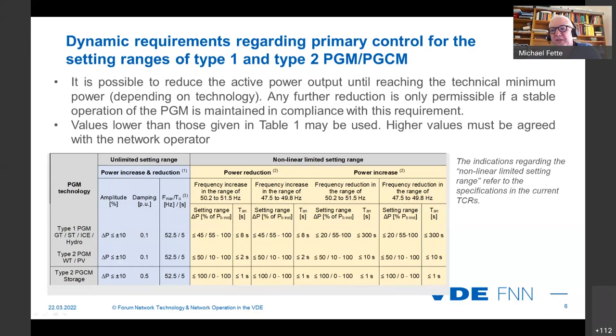We are looking exactly for the damping characteristics which each controlled unit could contribute to the grid. Therefore we asked the manufacturers, how good and how able are your plants, your PGMs, and how could they support the grid? In which case should they do that? And which portion of damping can they add to the grid behavior? These are questions which are very difficult to answer. We know from the manufacturers that some have no idea how to answer these kinds of questions, especially the smaller manufacturers or those of smaller inverter-based plants, since they have never tested or measured them in the complete range. What does it mean in the closed loop behavior?